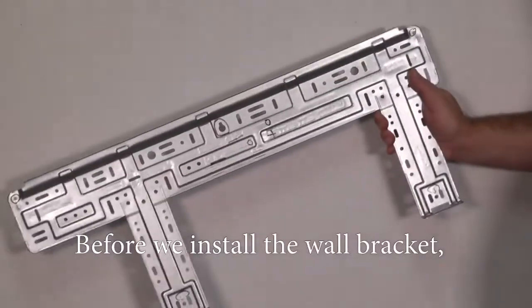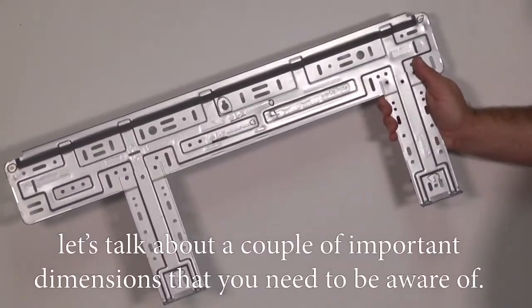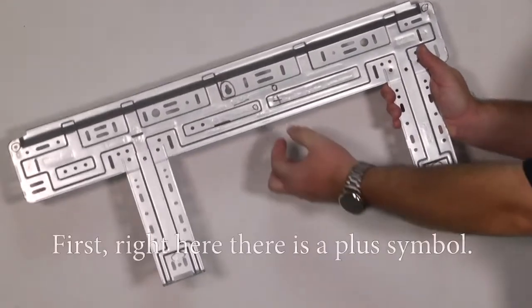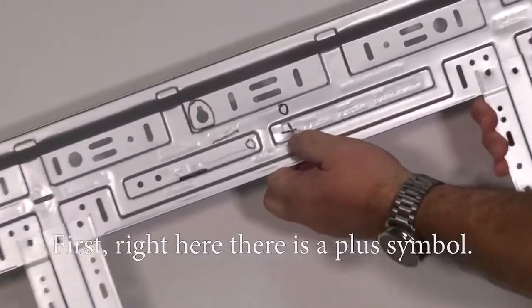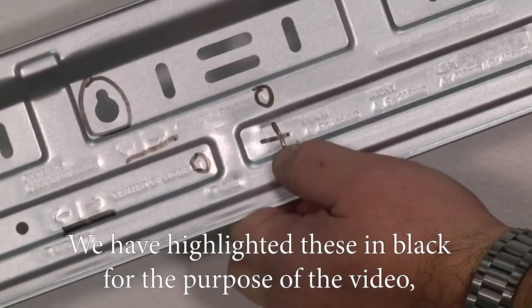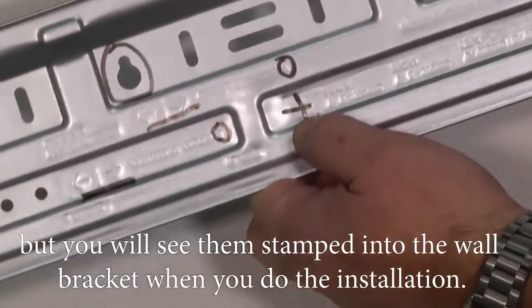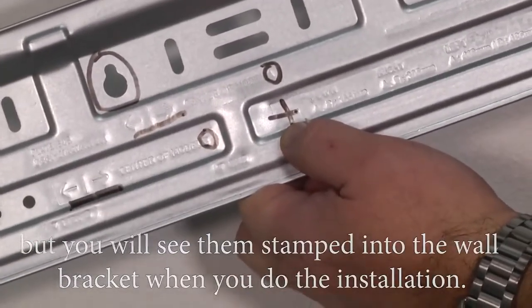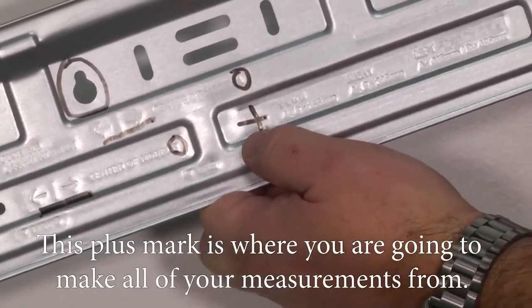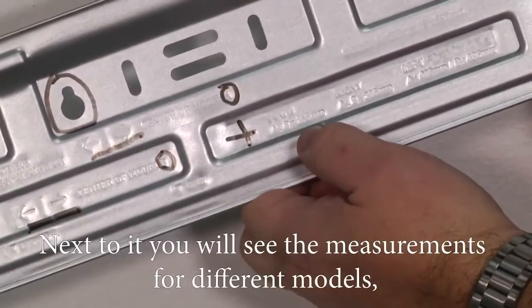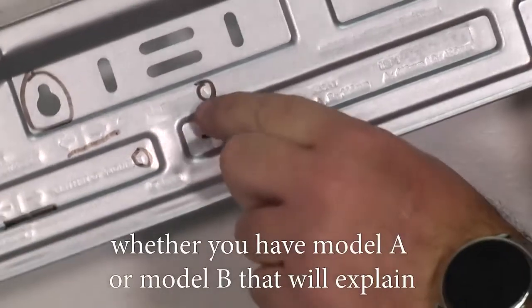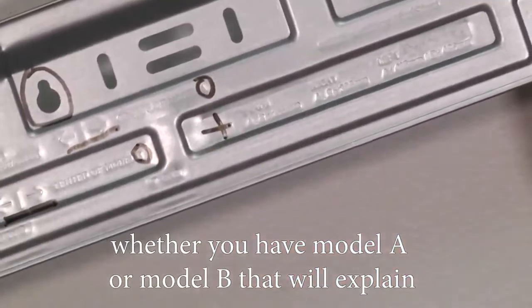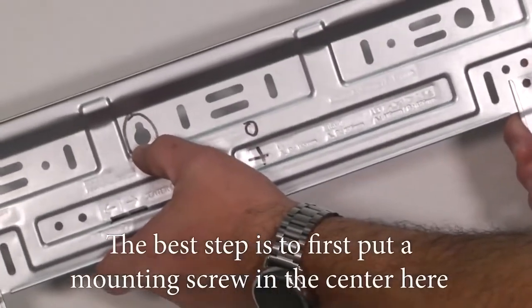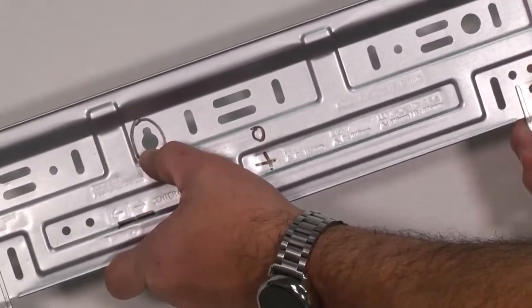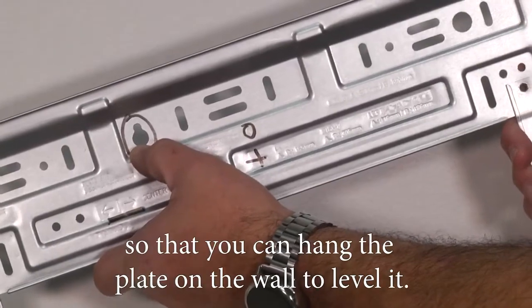Before we install the wall bracket, let's talk about a couple of important dimensions that you need to be aware of. First, right here there's a plus symbol. Now, we've highlighted these in black for the purpose of the video, but you'll see them stamped into the wall bracket when you do the installation. This plus mark is where you're going to make all of your measurements from. Next to it, you'll see the measurements for different models, whether you have model A or model B, that'll explain where you're going to put your mounting holes. The best step is to first put a mounting screw in the center here so that you can hang the plate on the wall to level it.